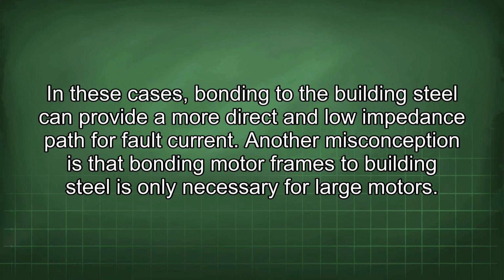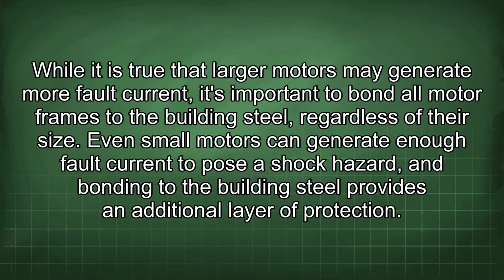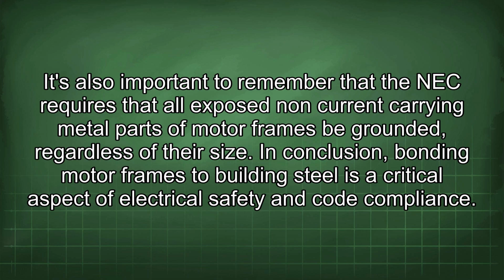Another misconception is that bonding motor frames to building steel is only necessary for large motors. While it is true that larger motors may generate more fault current, it's important to bond all motor frames to the building steel, regardless of their size. Even small motors can generate enough fault current to pose a shock hazard, and bonding to the building steel provides an additional layer of protection. It's also important to remember that the NEC requires that all exposed non-current carrying metal parts of motor frames be grounded, regardless of their size.